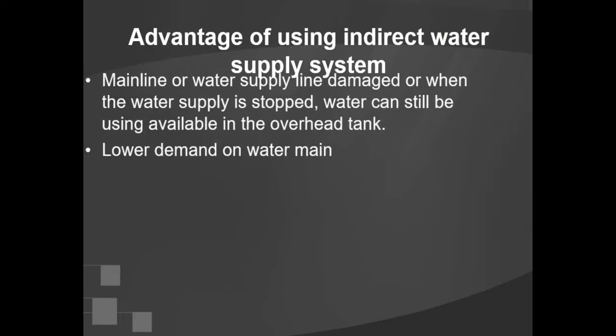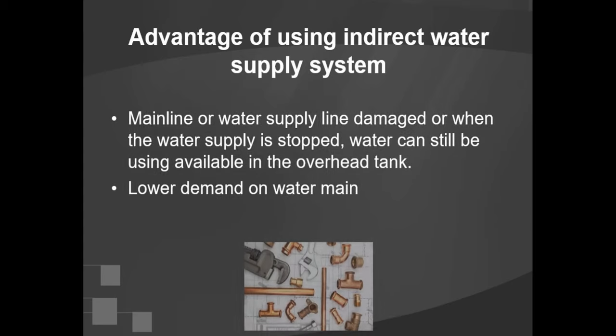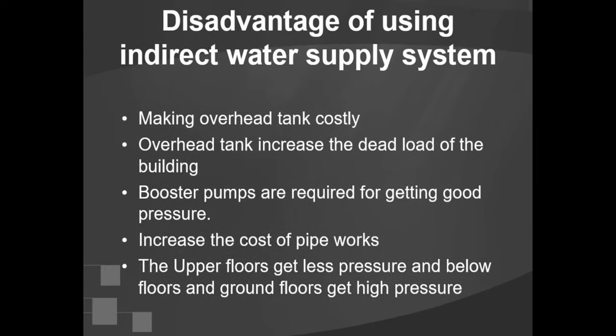The indirect water supply system has some advantages. When the main water supply line is damaged or water supply is stopped, water can still be used from the overhead tank. It also results in lower demand on the water main. Disadvantages include the overhead tank being costly to construct, booster pumps being required for good pressure, increased cost of pipe works, and upper floors receiving lower water pressure compared to ground floors.